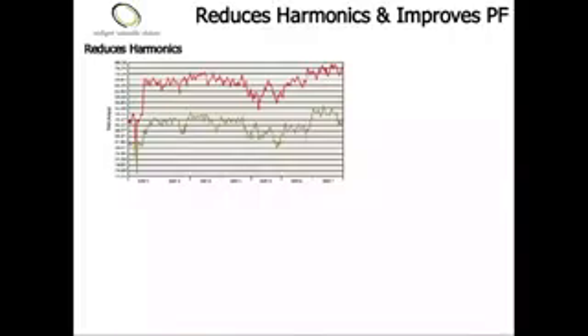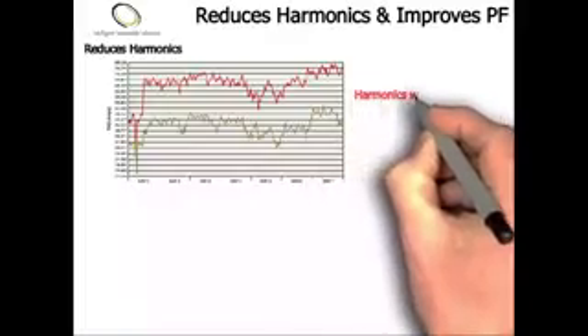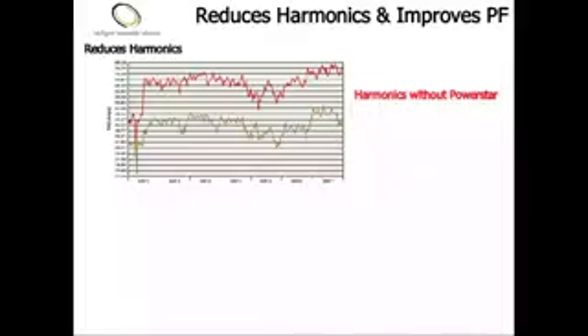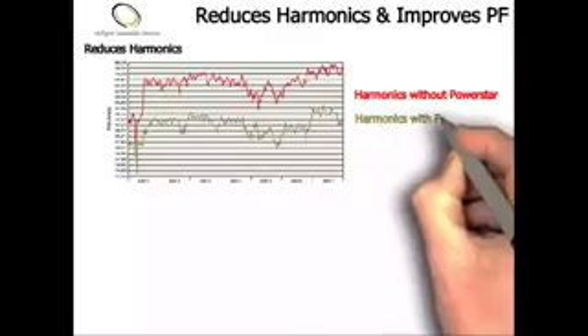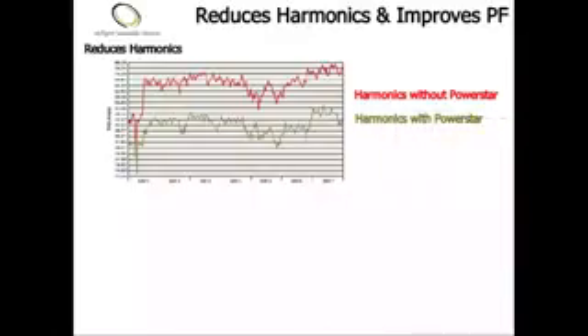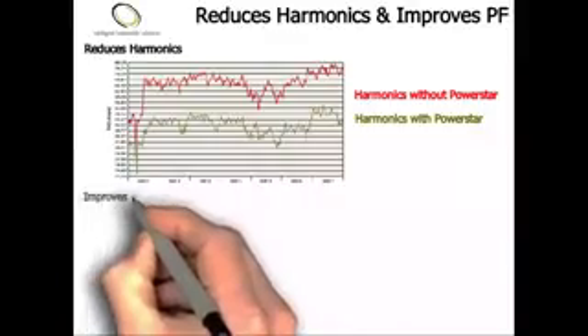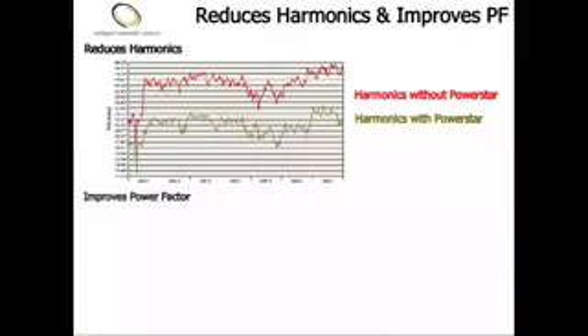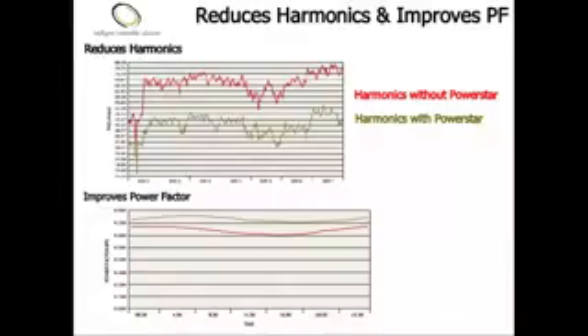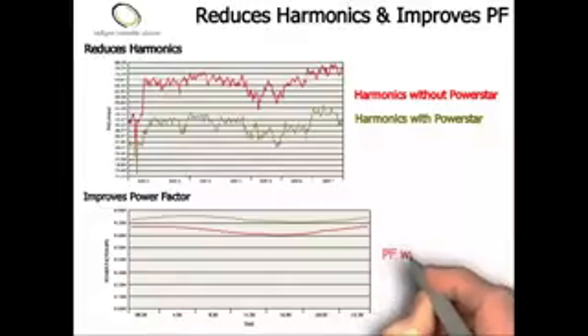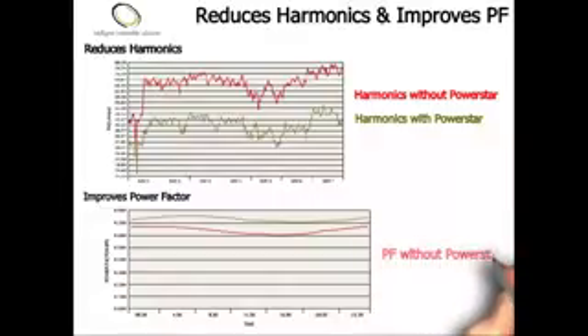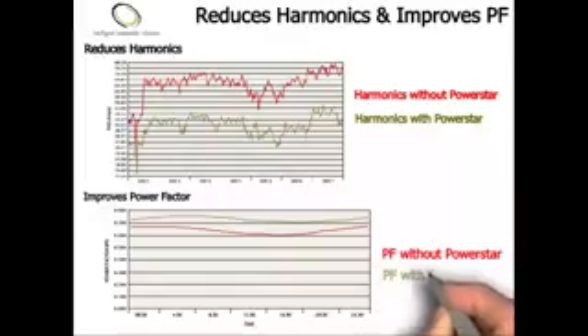One of the advantages of using PowerStar is the reduction of harmonics, typically the triplen harmonics. Here's a before and after of the total harmonic distortion, harmonics without PowerStar and harmonics with PowerStar. And here we have an example of PowerStar contributing to improving the power factor. Where there is high fluctuating voltage and a large consumption of electricity on site, power factor correction equipment and/or electrical filters should be utilized in conjunction with PowerStar.